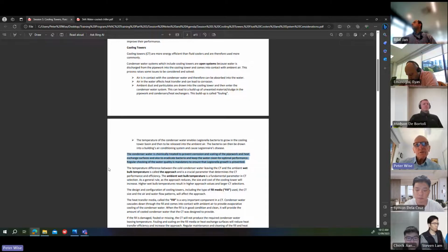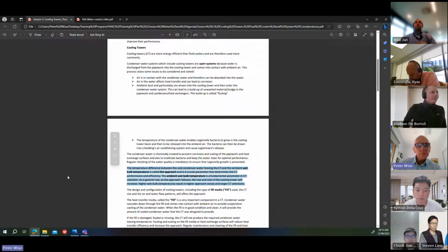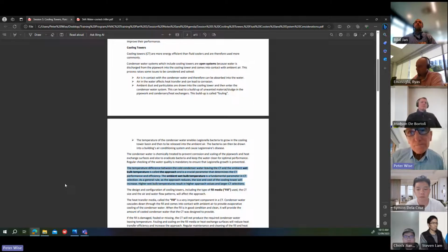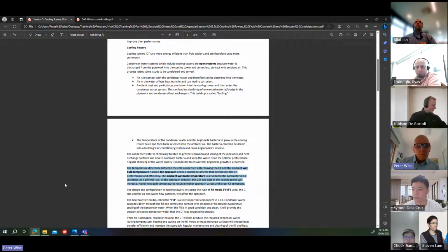The condenser water is chemically treated to prevent corrosion and scaling of the pipework and heat exchange surfaces, and also to eradicate bacteria and keep the water clean for optimal performance. Regular checking of the water quality is mandatory to ensure that Legionella growth is prevented. So the local councils will require that the maintenance is done on a regular basis and records are kept on site so that they can be checked to make sure everything's being done correctly. It's also our job at times to make sure that that's happening. So if we've got a water treatment company looking after the cooling towers, we may ask them to provide their reports when they do the cleans to ensure that everything's under control.